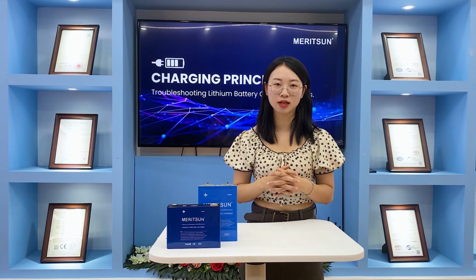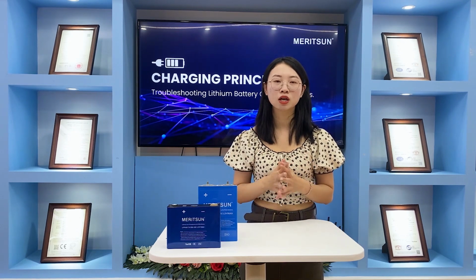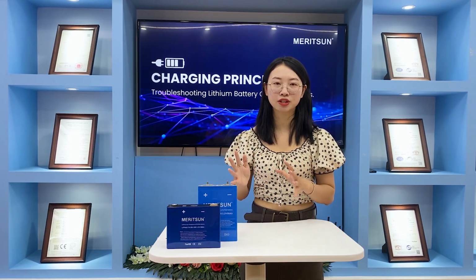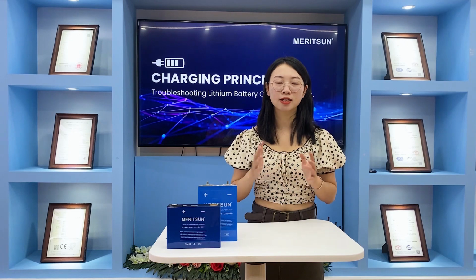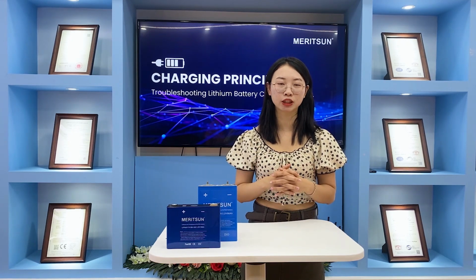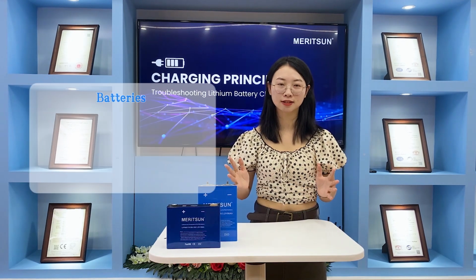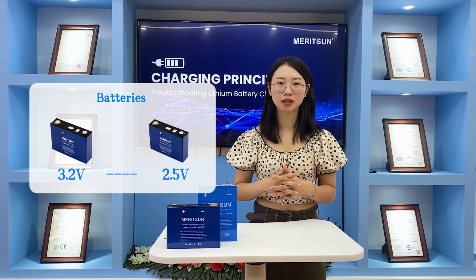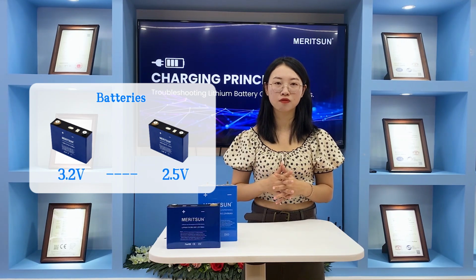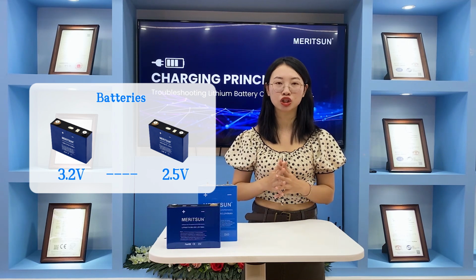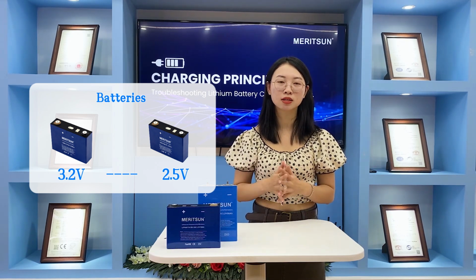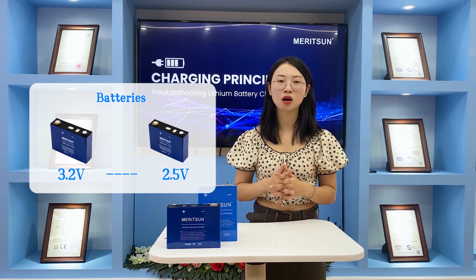However, if we can prevent over-discharge during use, it can best protect the battery. To achieve this, MeritSun's batteries are equipped with a BMS designed to safeguard against over-discharge. For instance, in a battery comprising 3.2 volt cells, if the voltage of a single cell drops as low as 2.5 volts, the BMS will intervene by cutting off the discharge process. This measure ensures the safety and longevity of the battery.